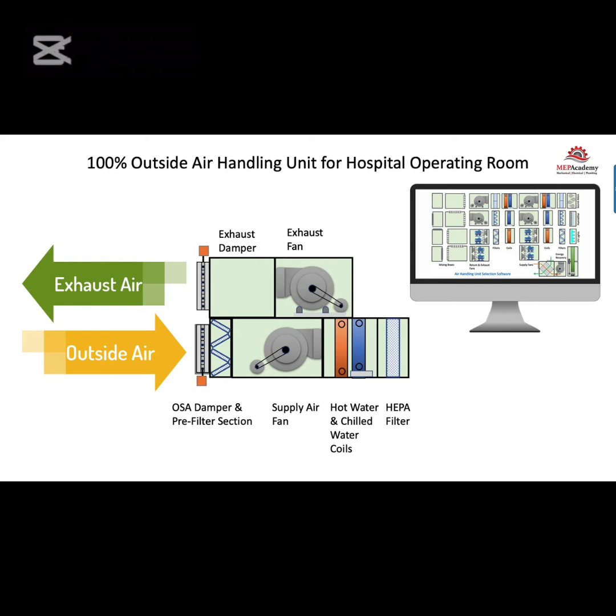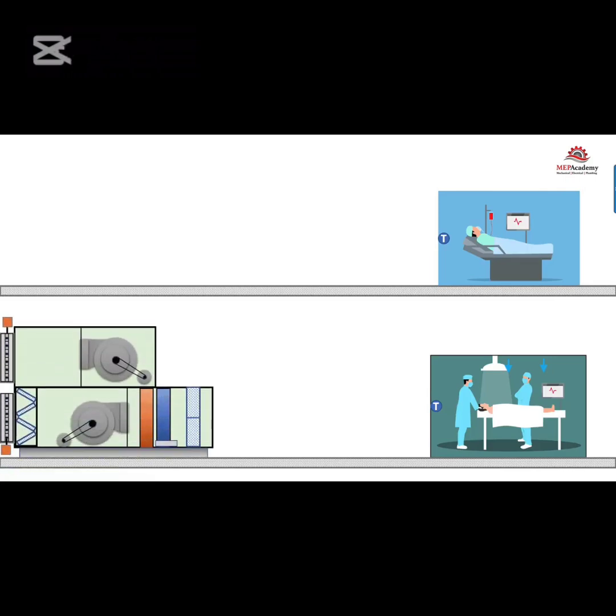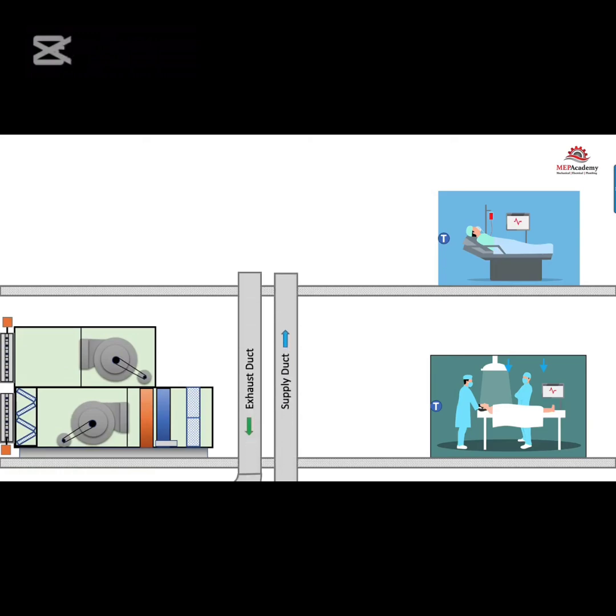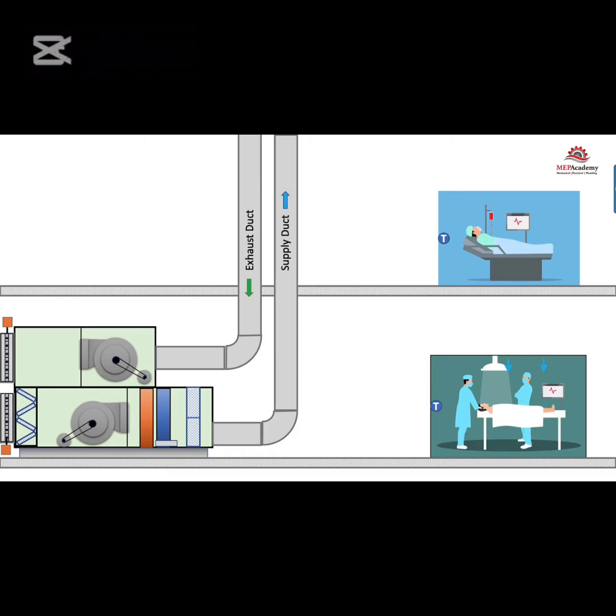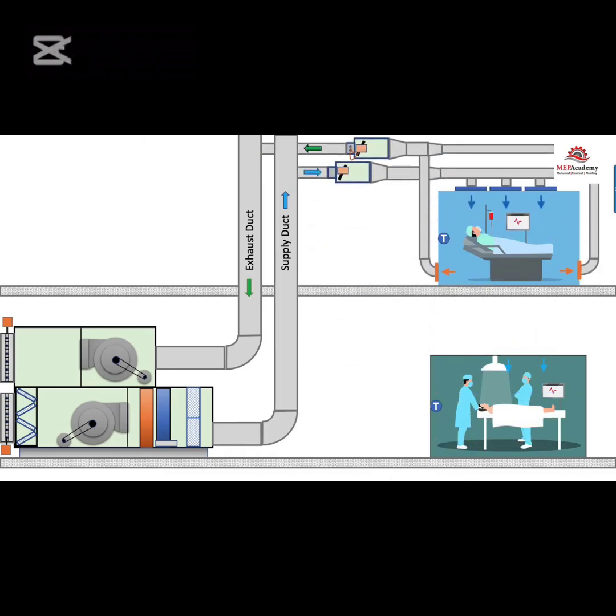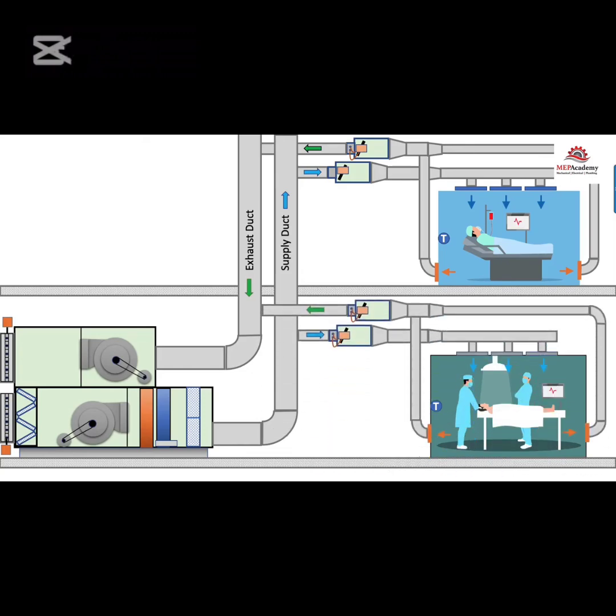Now we'll take that air handler that we've built and put it in the actual room. The contractor will set it into the mechanical room in the hospital. You see we got our 2 operating rooms there. We'll set our air handler that we just built, and then the contractor will run the main ducts, the exhaust and supply mains, and from there they'll tie in the branches through exhaust and supply valves, feeding the operating room with laminar flow grills and low return. And then we have our second operating room with the same exhaust and supply valves, same high ceiling supply, laminar flow across down over the body to keep the germs and everything down and out low, exhausting low.